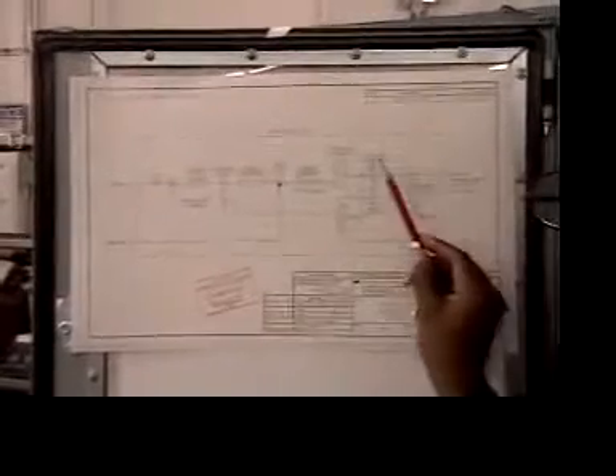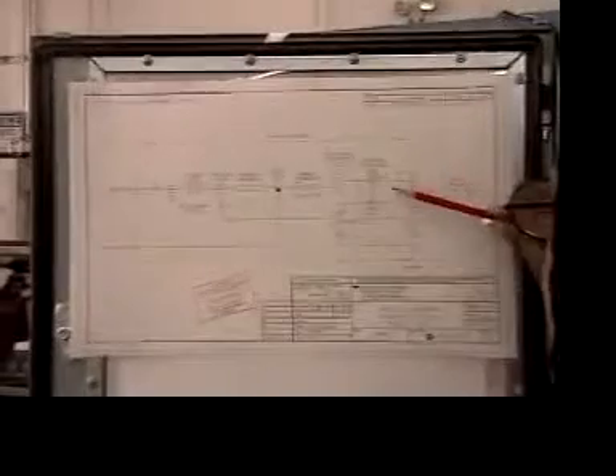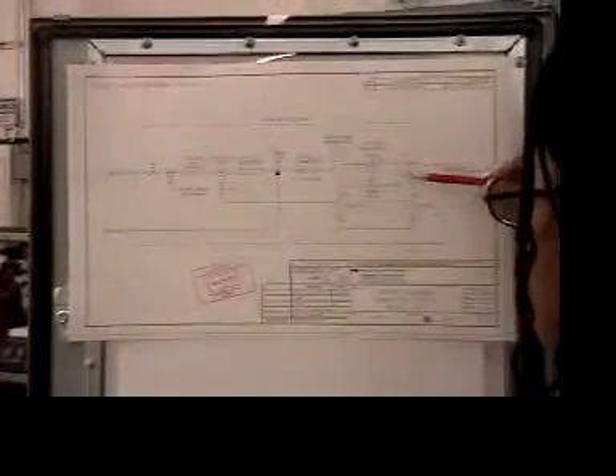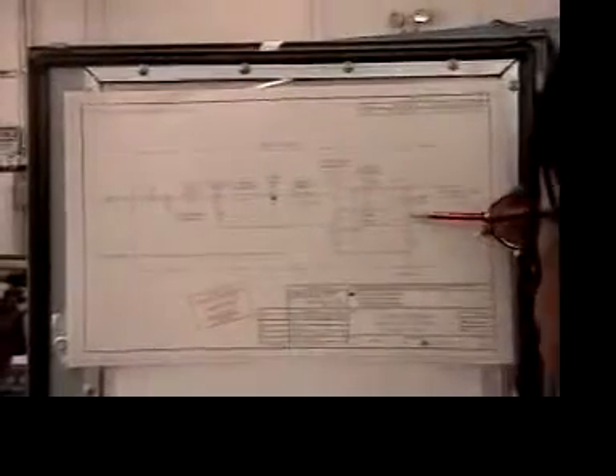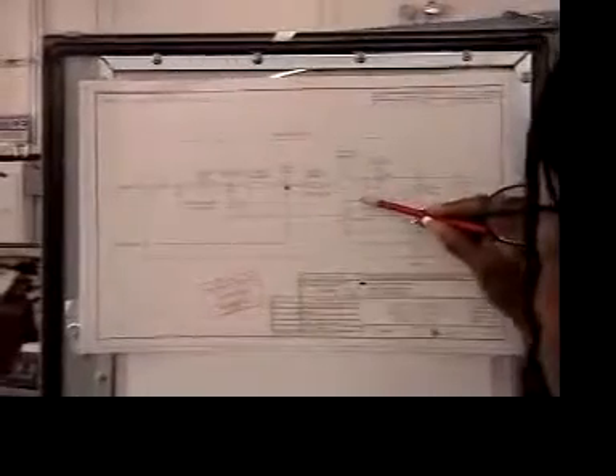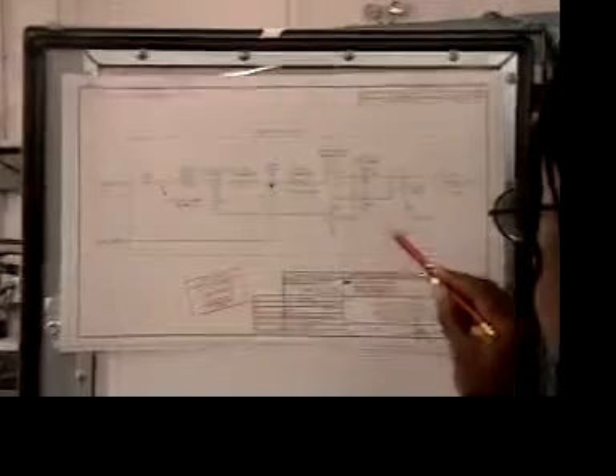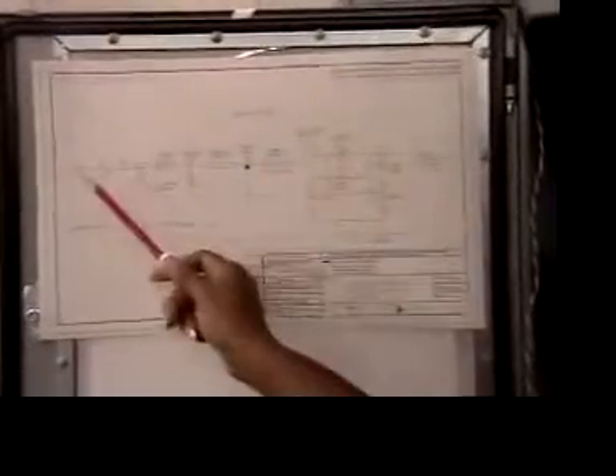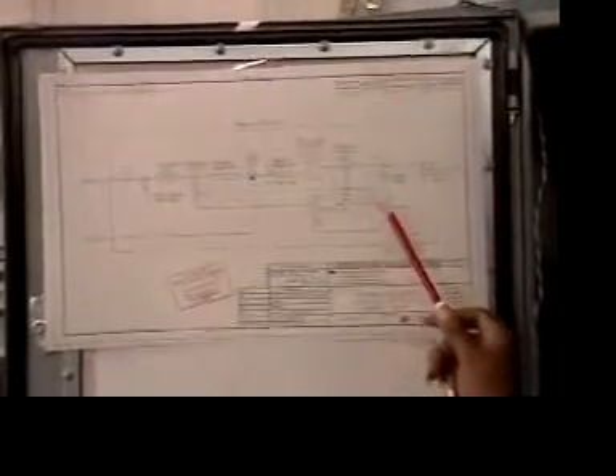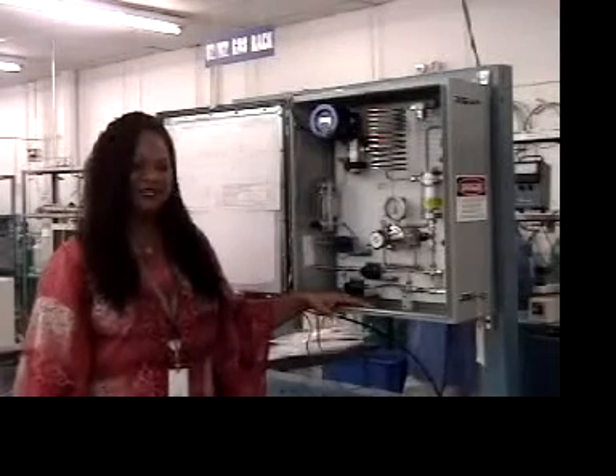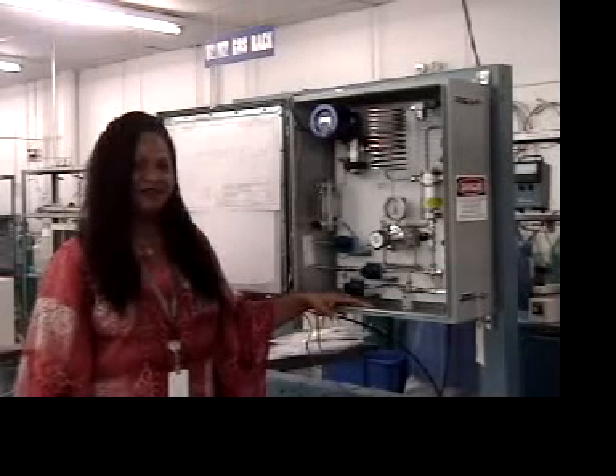Between the nitrogen or natural gas input and the vacuum regulator, there's a T which branches off in two different directions, both leading to a valve, V1 and V2. Valve V1 leads to the red input of eductor E1, while the line from valve V2 leads to the red input of eductor E2. Both inductors exit to a common exhaust. So the sample comes into the analyzer, being pulled in by the eductor system, flows through the analyzer, and back out to the eductor and vents to the exhaust. And this concludes our demonstration on the Insta with the sample handling system. Thank you very much.